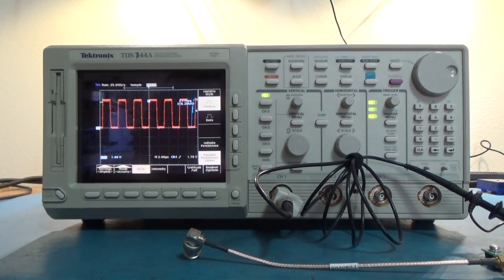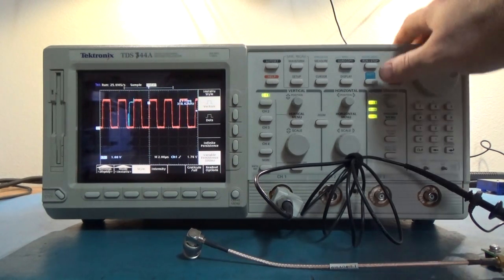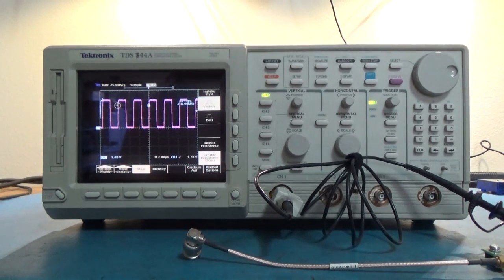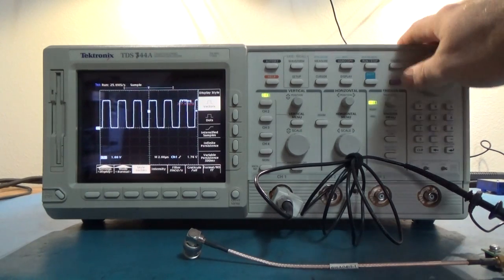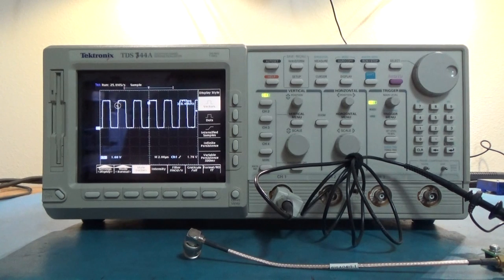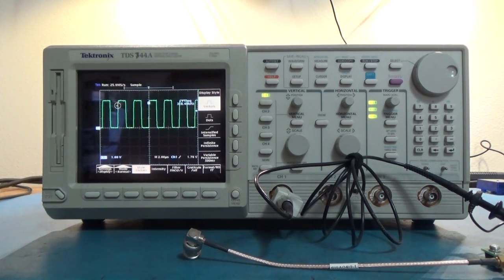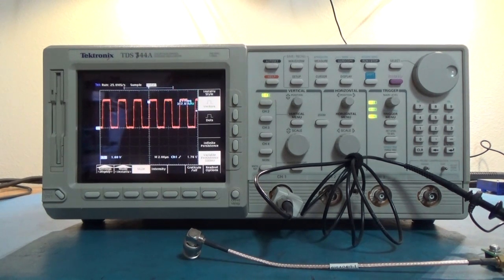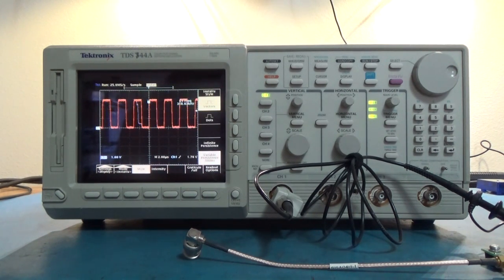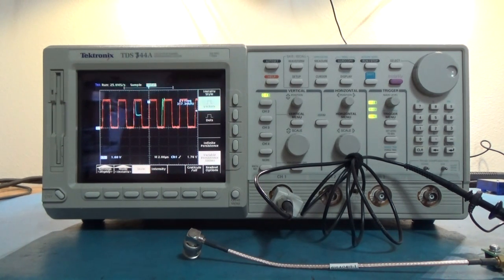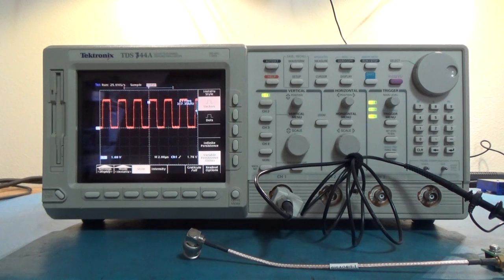This scope is pretty much the same as a 754A. The 754C will transition from InstaVu to non-InstaVu faster than what this one will. The transition would be almost instantaneous on a 754D, and you'd be wondering what's wrong with the 744A. That's really about the difference in what you're paying for. The 754D probably had applications that you couldn't get on the 744A.